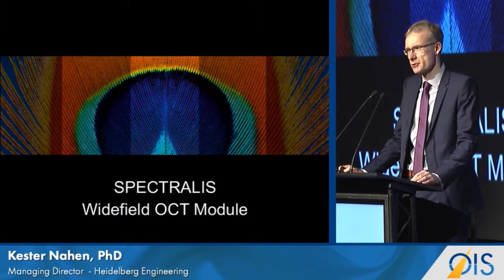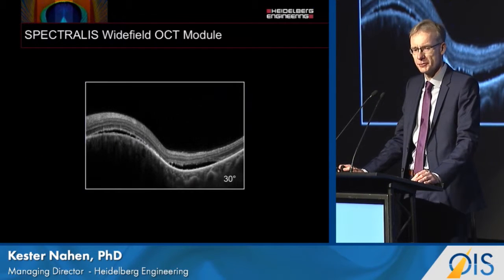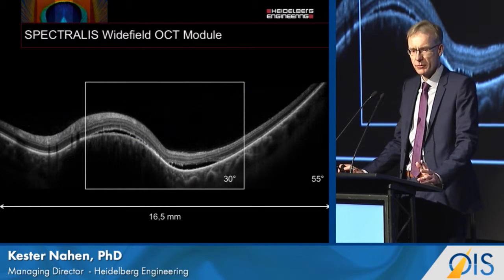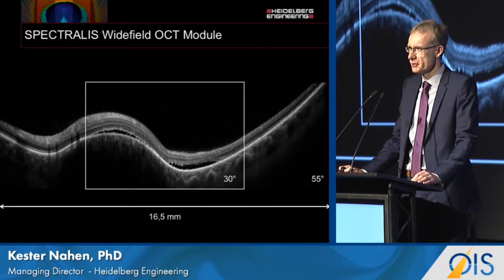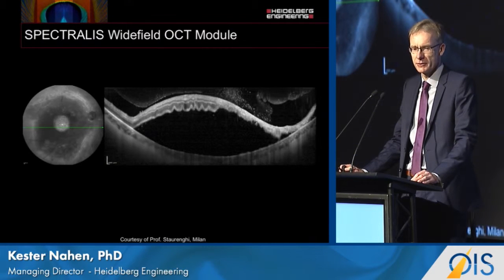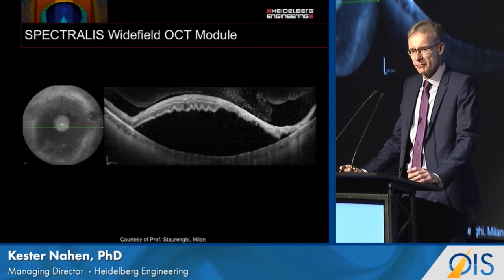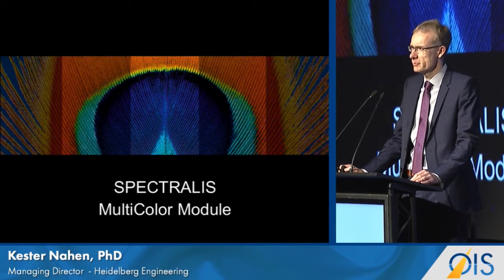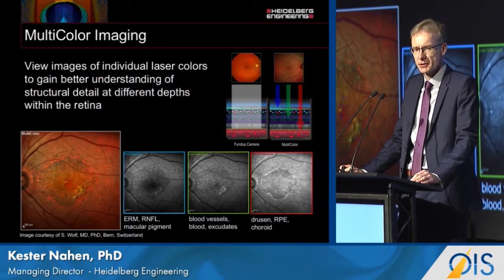The Spectralis wide field OCT module extends the field of view from 30 degrees out to 55 degrees, just with the addition of a software package to existing units, giving a scan width of 16.5 millimeters. With that, retinal specialists can visualize even extended retinal detachments.